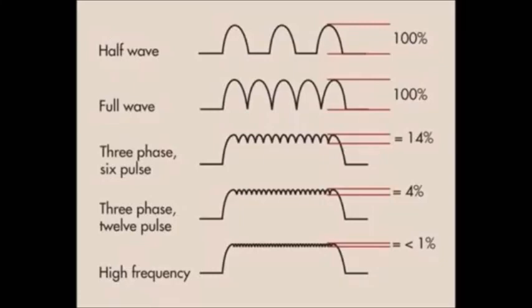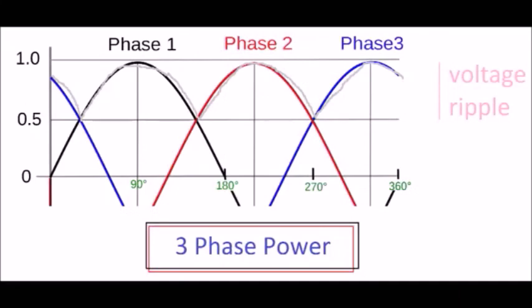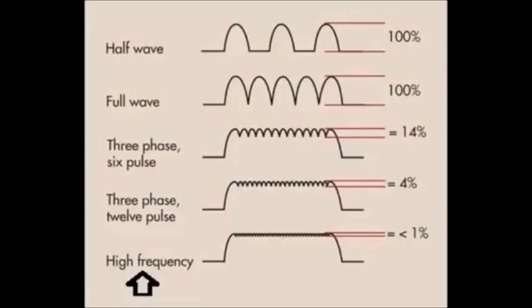X-rays produced when the voltage is near zero have little penetrability and have low diagnostic value. Three-phase power solves this issue by overlapping waves so that when one is losing voltage the other is peaking, meaning power never drops more than 14%. High-frequency generators attain less than 1% ripple and are used in mammography and CT.